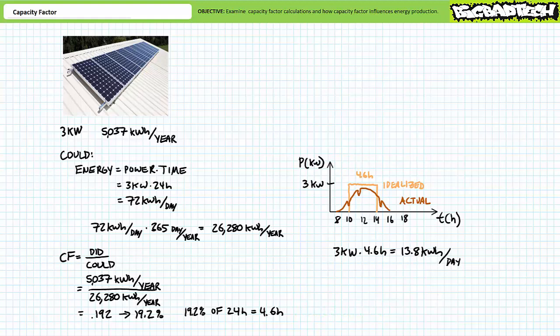Those of you with a calculus background will realize the energy output of the array each day is the area under the power curve. 3 kilowatts times 4.6 hours yields a daily block of energy with an area of 13.8 kilowatt hours. If you squint your eyes just right, both scenarios, the real varying output in brown and the mathematical equivalent light orange yield the same energy output, area under the power curve, albeit the calculations employing the peak sun hour simplification is much, much easier.